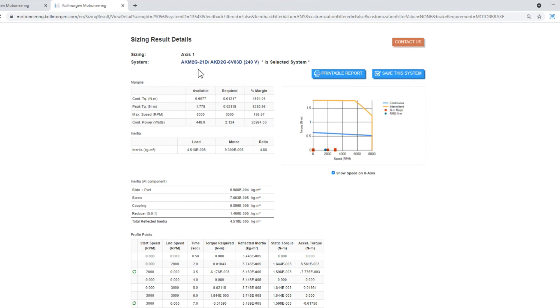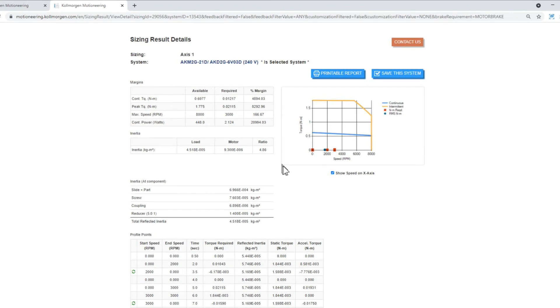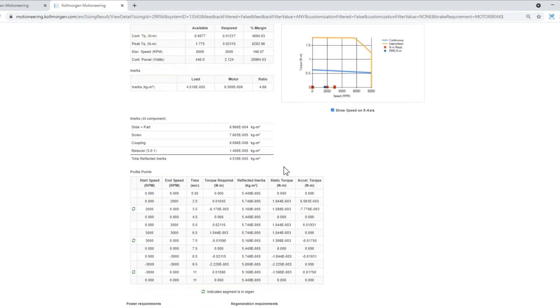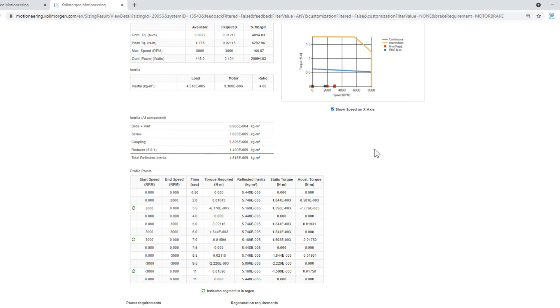The sizing results details will show the available, required, and percent of margin. If the system had exactly enough torque and speed, the margins would be 0%. If the system has twice the torque and speed, the margin will be 100%. In the middle of the page are the inertias for all the components in the system. It will also display the total reflected inertia of the system.